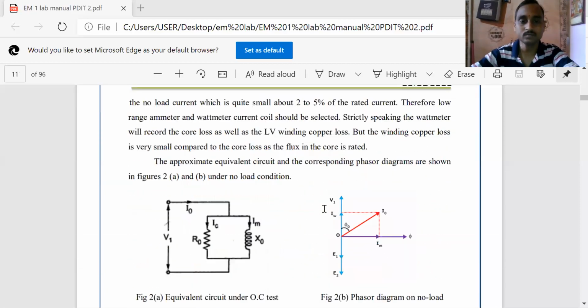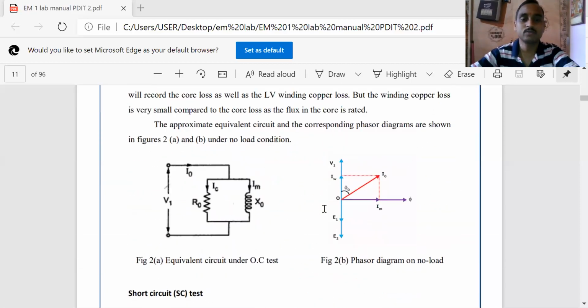And the equivalent circuit for the OC test: we have supply voltage V1 and we have R0 and X0. Due to R0, the IC is flowing here. IM is flowing through X0. So that can be drawn through the phasor diagram. IC can also be represented by IW, which is called the working current or core loss current. I0 is the combination of IW and I mu, or of IC and IM. IC and IW are the same, and IM is also called I mu, the magnetizing component.